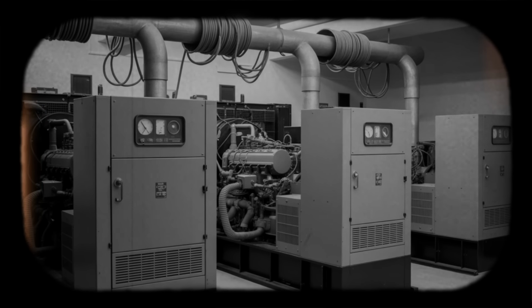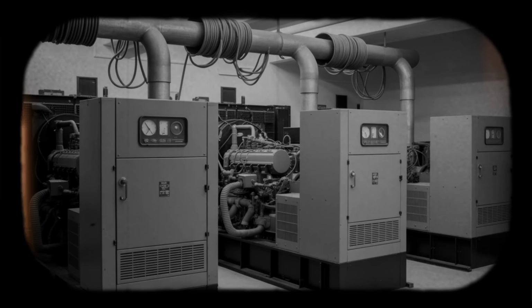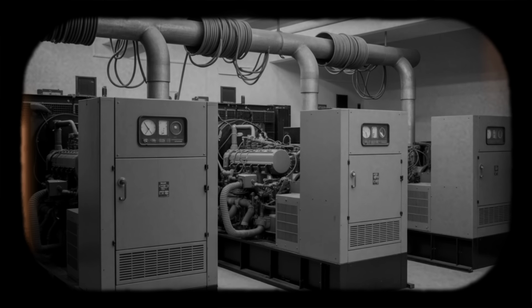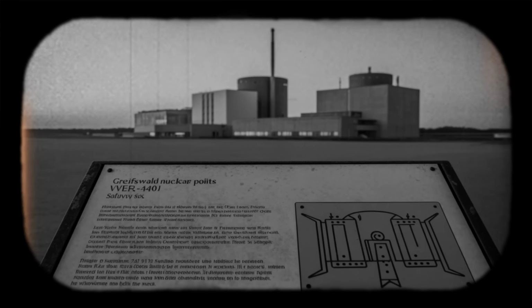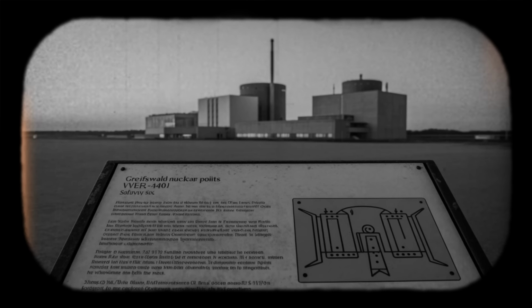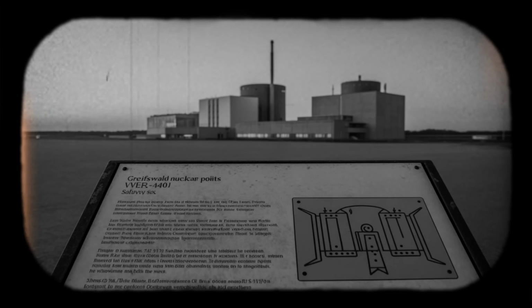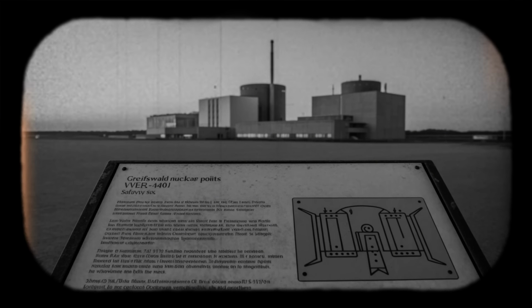WENRA, the Western European Nuclear Regulators Association, examined nuclear safety in candidate countries seeking European Union membership. Their 2000 paper cited two major blackout incidents, the Greifswald 1 fire in 1975 and Armenia 1 fire in 1982, as evidence that VVER 440-230 designs possessed both surprising robustness, the plants survived, and troubling vulnerabilities. Survival required extraordinary operator actions and fortuitous circumstances. The contrast was stark. On one hand, VVER 440 thermal hydraulic design, large coolant inventory, 6-loop configuration, and passive natural circulation proved resilient. On the other hand, electrical architecture, cable routing, fire protection, and instrumentation design showed deficiencies in redundancy and diversity.